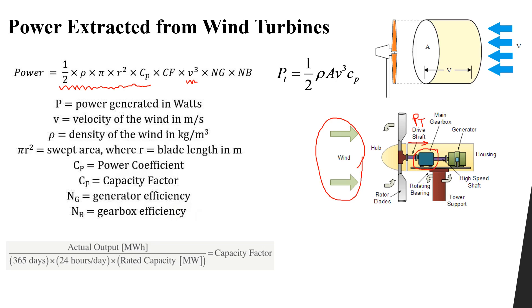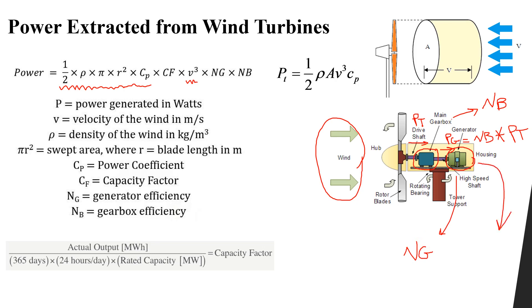Now we have a gearbox system with its own efficiency, called eta-b. The power input to the generator equals eta-b — the gearbox efficiency — multiplied by the turbine power. Our generator itself also has an efficiency eta-g, so the final output power from the generator equals eta-g times the power coming from the gearbox.